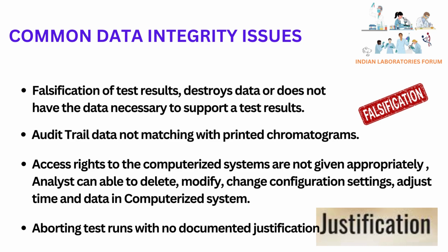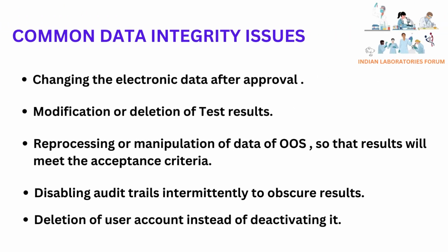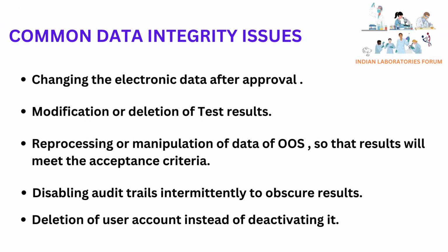Access rights to the computerized systems are not given appropriately. Analysts are able to delete, modify, change configuration settings, and adjust time and date in the computerized system. Aborting test runs with no documented justification. Changing the electronic data after approval.